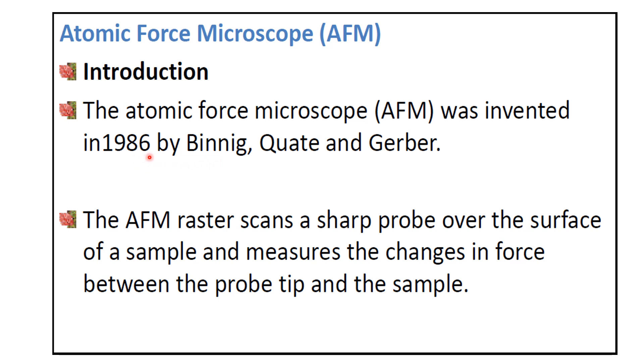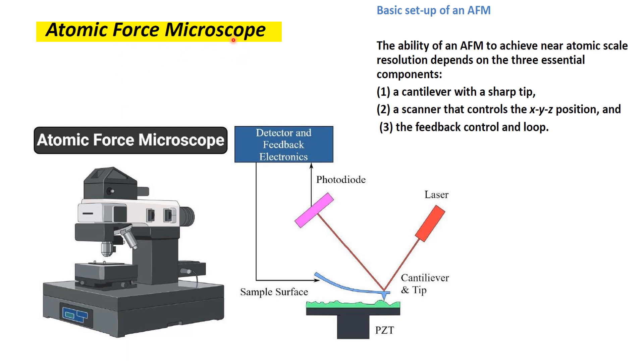Now we discuss atomic force microscopy (AFM), which was invented by Binnig in 1986. In AFM, atomic forces are measured as the probe scans the sample. It is a tabletop device and does not require any vacuum. The components include a PZT (piezoelectric) crystal platform on which the sample is placed, a cantilever with a tip, a laser light that falls on the tip, and a photodiode detector.